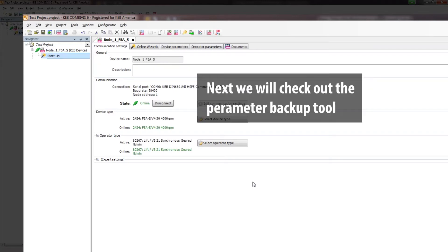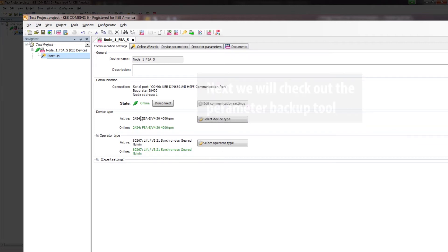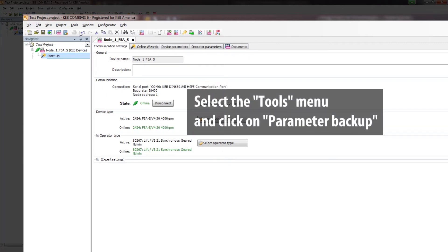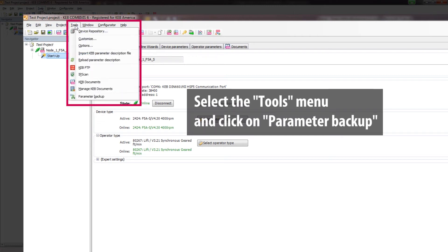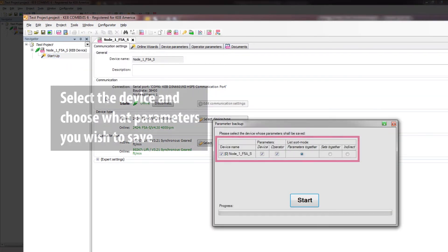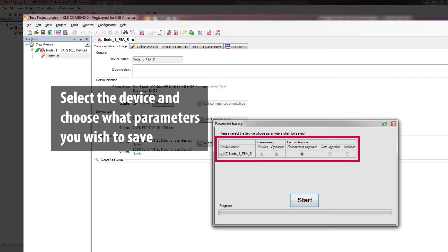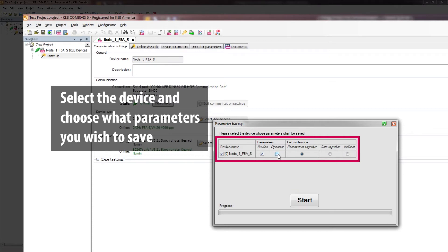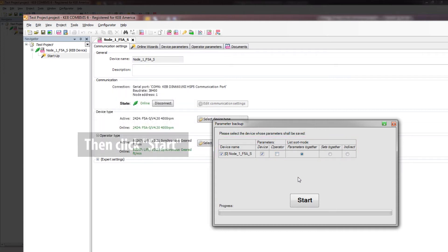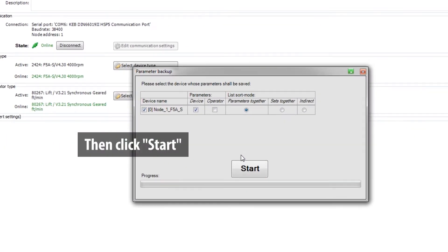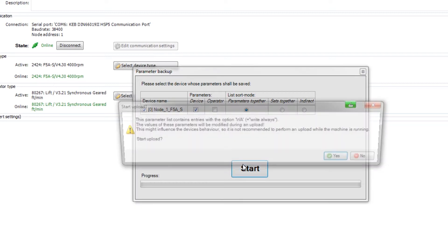If you want to take an upload of the parameter settings that are in your inverter, you can use the Parameter Backup tool. From the Tools menu, select Parameter Backup. Select your device and choose whether you want to save just the device parameters, the operator parameters, or both. Generally, the easiest way to save the parameters is with the option parameters together. Once you have selected the desired options, click Start.